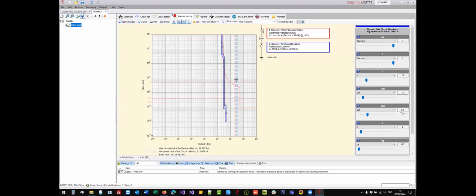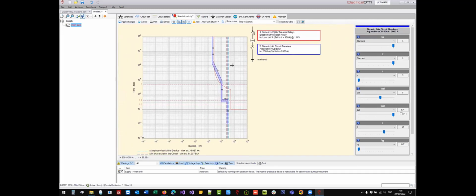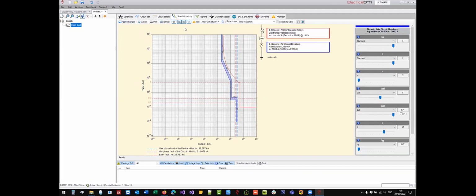And as Mike already mentioned, a selectivity study, so a coordination and arc flash study, should be considered at the same time because the one might affect the other. So what I will do now is go here to the coordination. I will make some adjustments to this breaker. I'm just doing them to consider some settings that might be used later on. And then, of course, I will modify this relay so it will not overlap with my low voltage air circuit breaker. So I will increase the time a little bit here. I might choose another setting for the first curve. And I can see now that the selectivity study shows no overlaps, so it's okay.